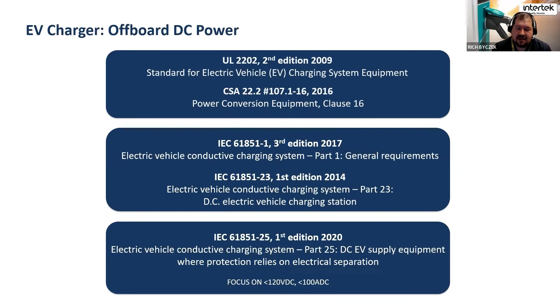There's also a -24, which I don't call out here, covering the communication protocol involved. I mentioned a -25 as well, which looks at protection relying on electrical separation. So there are different versions of systems for lower power versus higher power DC systems. Often we think of DC systems as high-powered 25 or 50 kilowatt systems, but if your vehicle only has a DC inlet, you may need a smaller off-board DC charger. That's the idea behind -25, to allow for more consumer-grade charging systems.